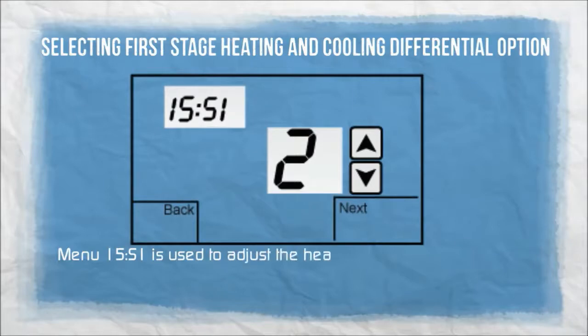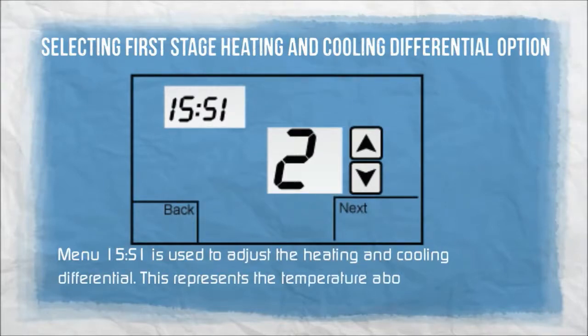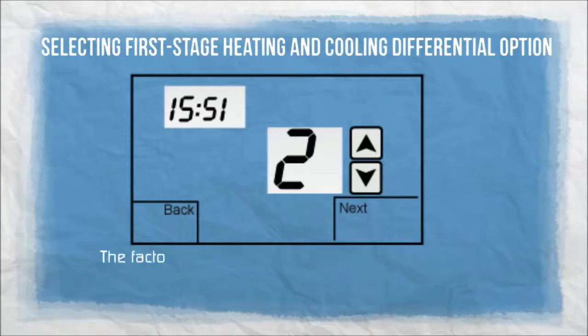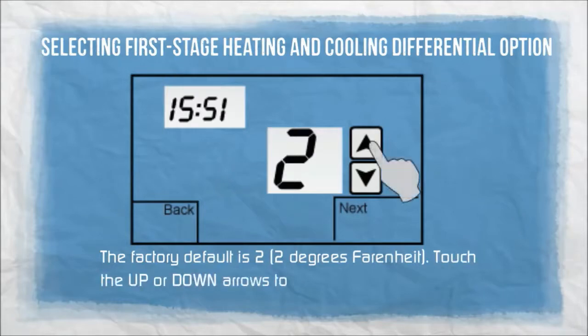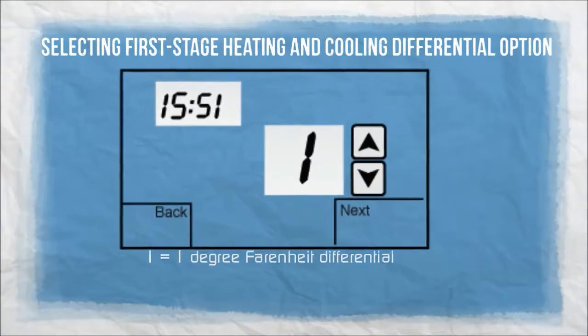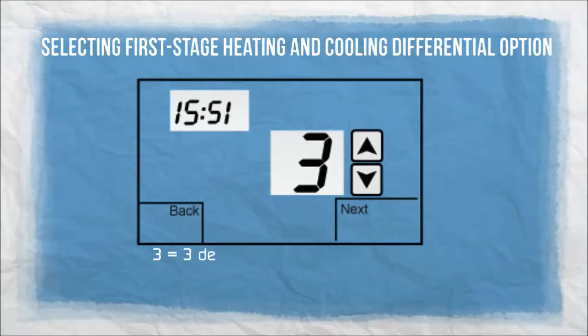Menu 15S1 is used to adjust the heating and cooling differential. This represents the temperature above the cooling set point or below the heating set point when the equipment is energized. The factory default is two degrees Fahrenheit. Touch the up or down arrows to change the differential. 1: one degree Fahrenheit differential. 3: three degree Fahrenheit differential.